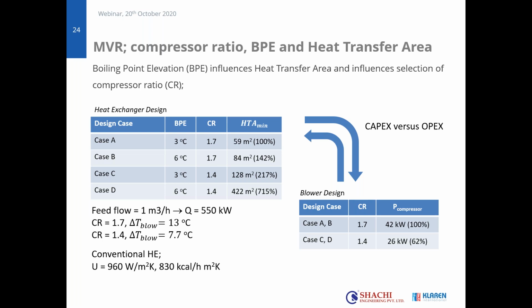square meters. But now we take the same case, and we know that the boiling point elevation is not 3 degrees, but 6 degrees. Then you see that this directly affects the heat transfer area that I require, because then it will be 84 square meters. So my really important message is that if you're a customer that wants to buy an MVR unit, please specify to all your vendors which boiling point elevation to use, because this will affect the design that they will give you. And at the end, if they assume it, they will take a low one, because then they need to provide less area. But at the end, your system could not work.